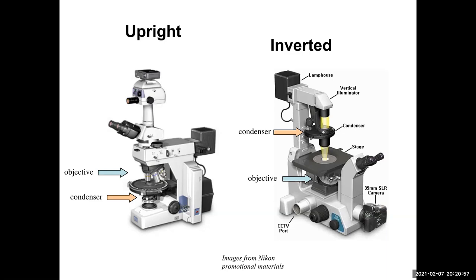The reason for the inverted scope design is that it's easier to access the specimen. In a regular upright scope, the objective is right there and you can't really manipulate your specimen. With an inverted scope, there's all that space on the stage — you could put a big fat dish of cells, for instance, which we do, and just focus up through the container of cells to find the one you want. This is basically a scope used for live cell imaging.